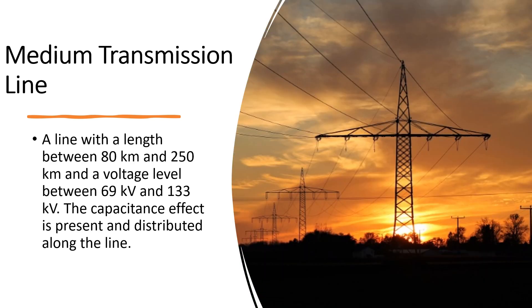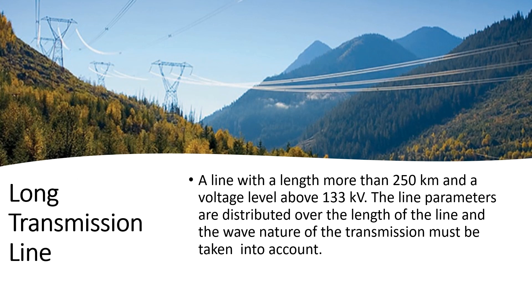A medium transmission line is a line with a length between 80 km and 250 km and a voltage level between 69 kV and 133 kV. The capacitance effect is present and distributed along the line. A long transmission line is a line with a length more than 250 km and a voltage level above 133 kV. The line parameters are distributed over the length of the line and the wave nature of the transmission must be taken into account.